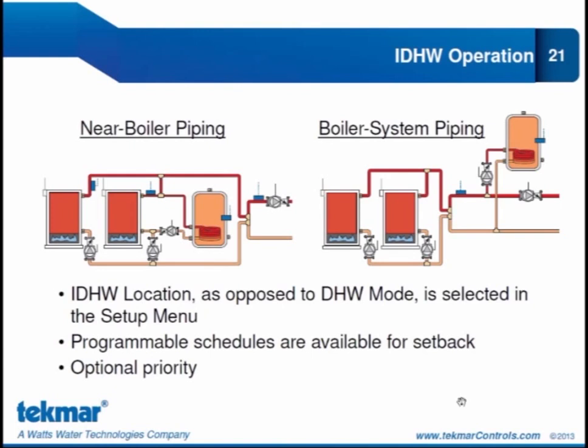I mentioned before the indirect domestic hot water operation and how it's important here to distinguish between near boiler piping and boiler system piping. Because in the 284 we are no longer using domestic hot water modes to configure the control. So in the past we would have chosen mode 1 up to mode 5. This isn't very intuitive for people. So if someone is trying to look at the control to readjust the control, those mode selections would require someone to refer back to their manual.